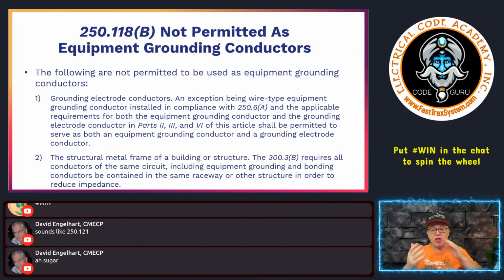So you see, in theory, this exception, again, works. Sorry about the noise, folks. It works very well for the PV systems, right? Not going to work real well to do this with the sub-panel remote distribution thing. So it's important to locate your electrodes near the main service equipment rather than think about doing it at a remote distribution panel. You get what I'm saying? But there are some allowances in here if you meet all this. You may not meet it. That's why it's an exception, okay?